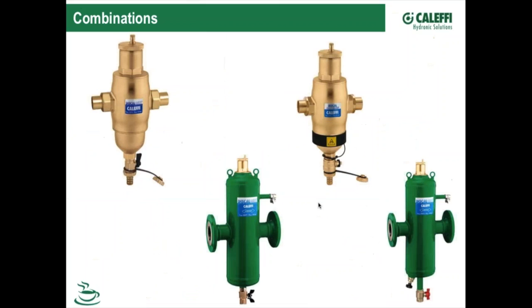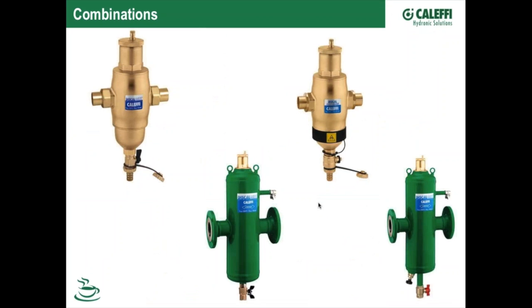So the combination devices. Now what we thought we'd do here is offer a device that can do both those things in one component. So instead of buying 2 different components, you just put it all in one box, so to speak. So you can see in the picture here, what we did there is we had the air separator and put the dirt separation portion on the bottom. It's a taller component here. We offer those in the smaller steel versions. We offer them also with the magnet on them. So now you've got the dirt separation, you've got the air separation, you've got the magnetic separation. Same thing in the steel version here.